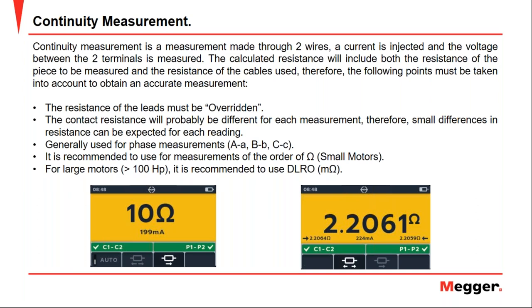This method is generally used to measure phase by phase, a single coil, and it's recommended, as we just said, to measure the resistance of the winding in small motors. If we need to do a measurement in a large motor with big winding, we have to do it with another method like the Kelvin method.